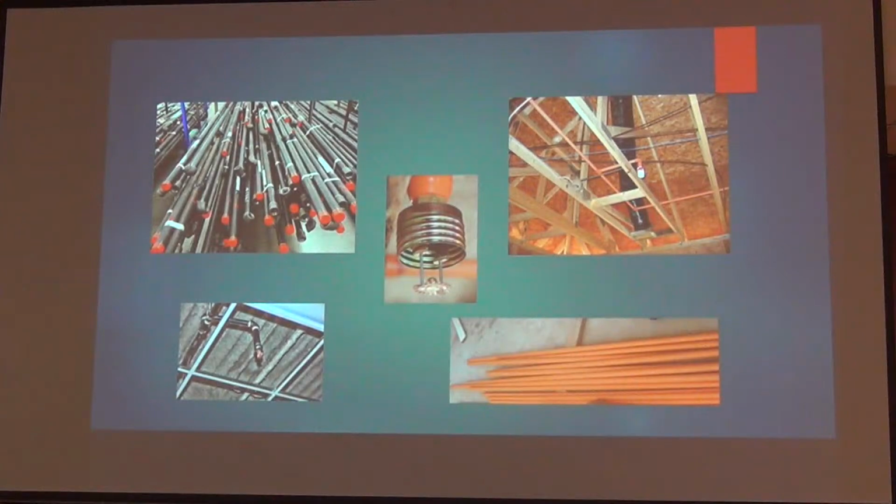Yes, sir. On that building, because of 3 stories above it and parking garage below, the top 3 floors or possible 4 floors are 13R, correct? And the lower level is always 13 in the parking garage in those situations. All right, correct, just verify. The lower level is considered an S use. All S uses have to be suppressed under 13, not 13R.